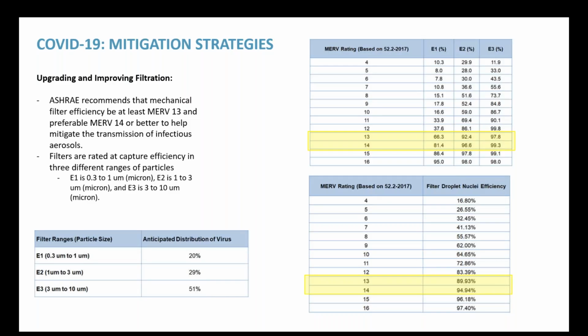So when we talk about remove, really we're talking about filtration predominantly. And so last year, ASHRAE had recommended that at a minimum you provide, where possible, MERV 13 filtration. And if you can achieve MERV 14, that's even better. Well, since then, they have provided additional information to understand how they came up with that recommendation. What they did is they took the best science that's available and started applying it to the way that these different MERV ratings are achieved. So there are 3 different size ranges for capture efficiency, E1, E2, and E3, and they go from smaller to larger particle sizes.